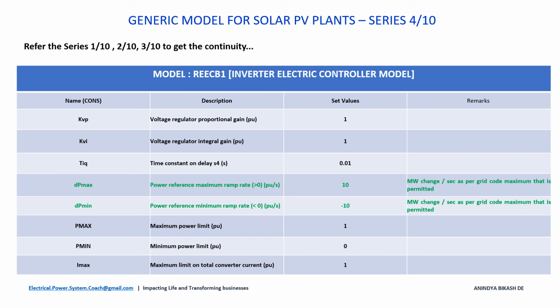Certain other parameters are there. Here the most important parameter is dp max and dp min. What is dp max and dp min? It is the megawatt change per second as per the grid code, maximum what is permitted and minimum what is permitted. So in every grid code it is specified that you can ramp up or ramp down the megawatt capacity, that certain limit is specified, and here the typical value we have put as 10 based on certain grid code, and on the project whichever has been considered, so based on that one.